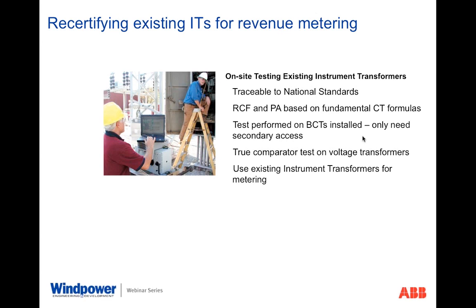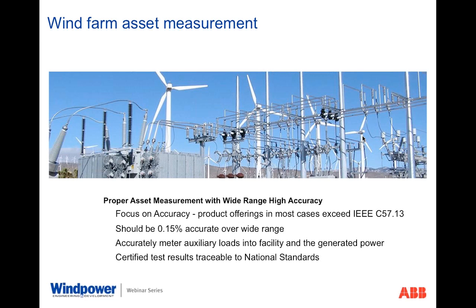So with this type of configuration, you can actually bring to bear CTs that were never intended to be revenue metering, bring them into the revenue metering application. For instance, we did that when Dominion joined PJM. We went in and recertified their facilities for revenue metering by using this technology. So there are methodologies out there today to be able to recertify CTs and VTs for revenue metering.